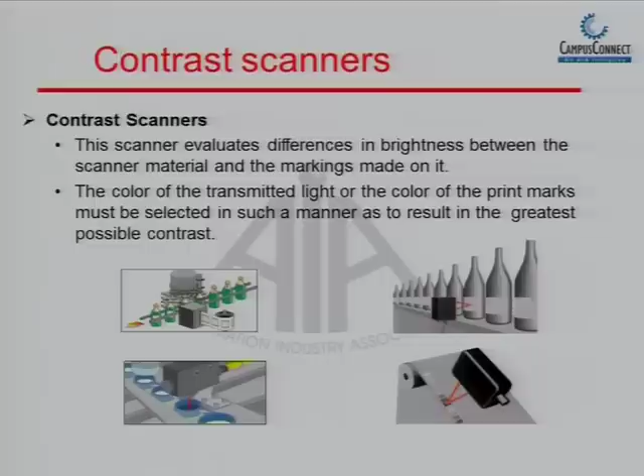Again, contrast sensors. In packet materials you must have seen a black mark on top of it, which we call an eye mark. It is supposed to sense the black mark so that the servo systems can do the cutting of the pouch. So we call this an eye mark sensor or a contrast sensor. It works on the principle of change in contrast of the target. That means the black color is the contrast and the background is of a lower contrast. So a change in the contrast ratio will give an output.